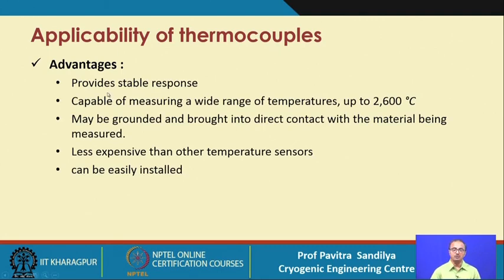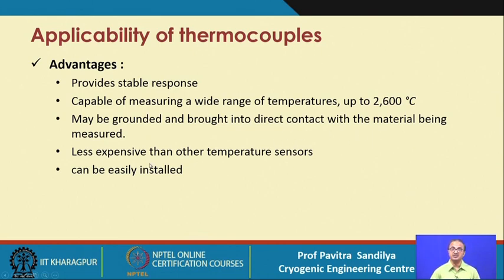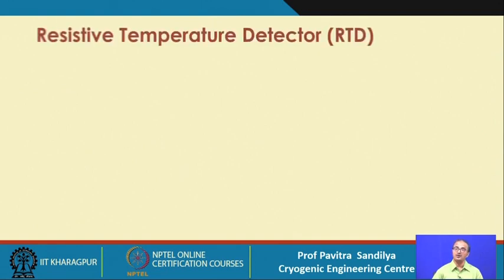Advantages of thermocouples: they provide stable response, can measure a wide range of temperatures, may be grounded and brought into contact with the material being measured, and are less expensive and easily installed. Disadvantages: measuring two temperatures simultaneously is less effective and can generate errors, but overall thermocouples are very commonly used in research.